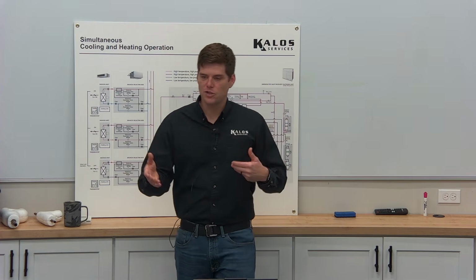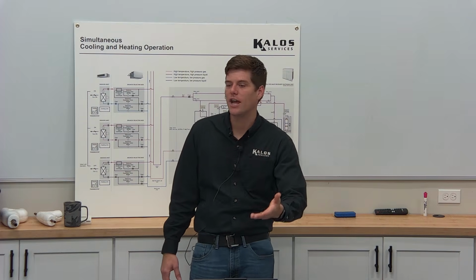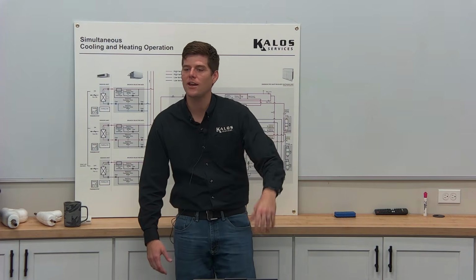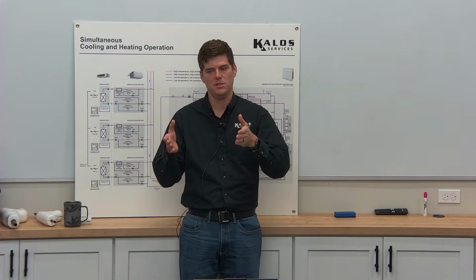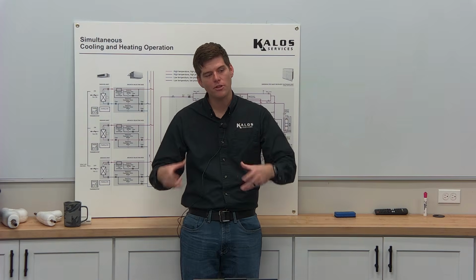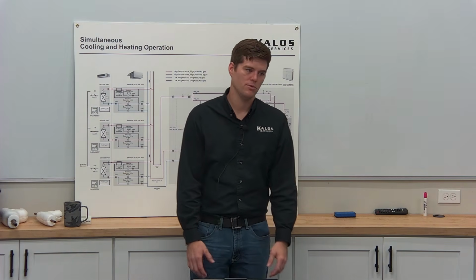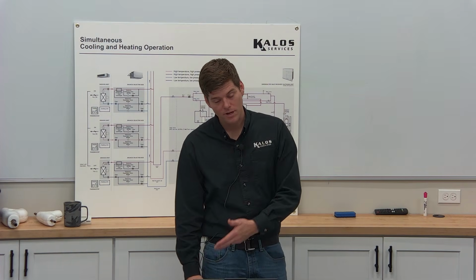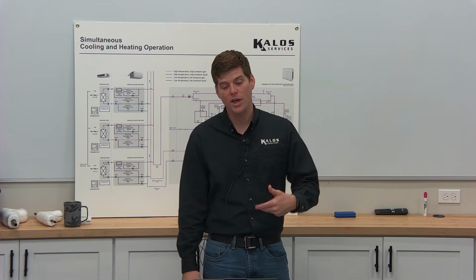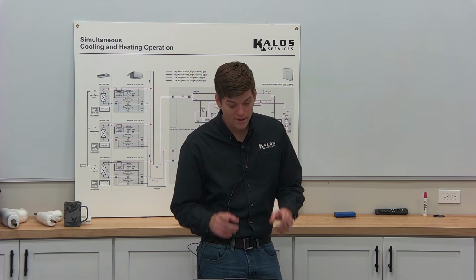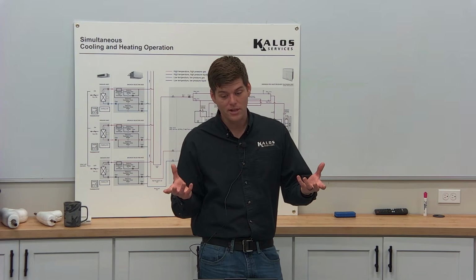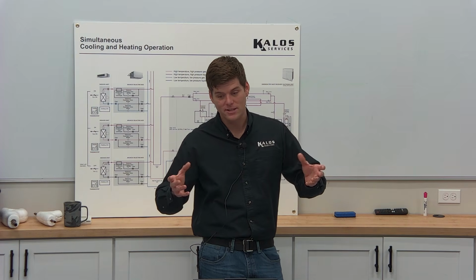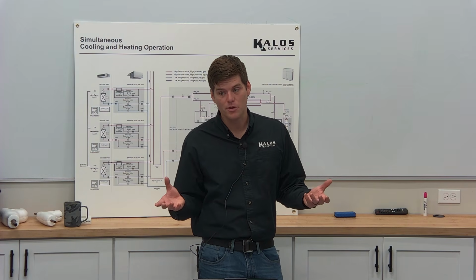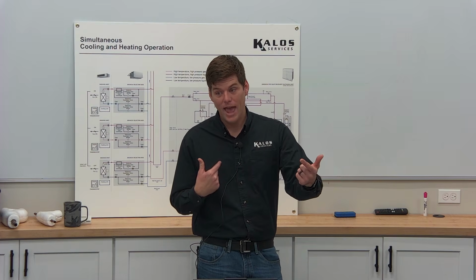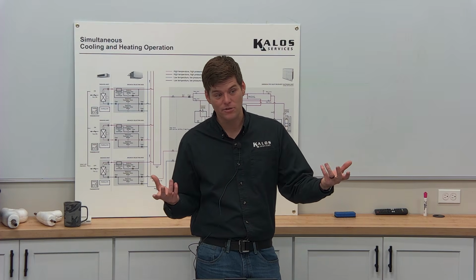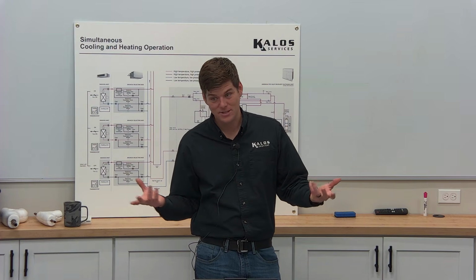Now, sure, the boards you can get to from the side, flared connections for refrigerant lines, drain line, everything's from the side, high voltage, all from the side. Right. But all the other major components for serviceability, it's from below, which is why it is so important to read the installation manual and see what the actual required service clearances are. You'll find that the service clearance for underneath a unit like that, sure, it fits and it's a great design, but I don't think a homeowner is going to be okay with a 48-inch by 30-inch access panel underneath a unit in the middle of their living room. It's just hideous, right? It doesn't make any sense.